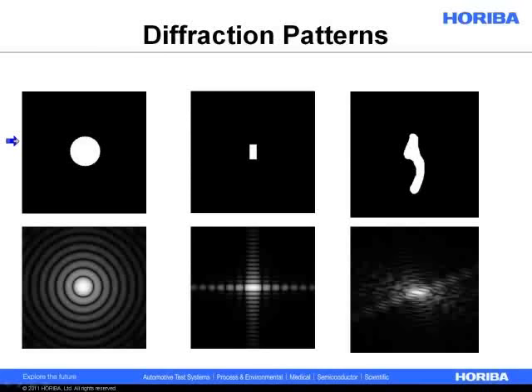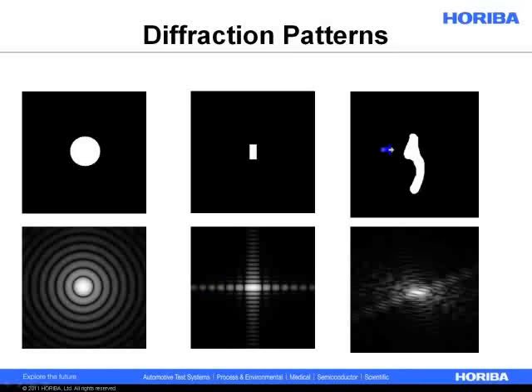The diffraction pattern depends on the shape of the particle. If you have a perfectly spherical particle, you'll get a very well-behaved, nice-looking diffraction pattern. If you have a well-behaved rectangular prism, you'll get another well-behaved diffraction pattern. But if you have a more realistic-looking particle that is very hard to describe using shape terminology, you'll get a mismatched diffraction pattern. This is much more the realistic case — the laser diffraction analyzer is measuring this and has to back out some shape measure from it.